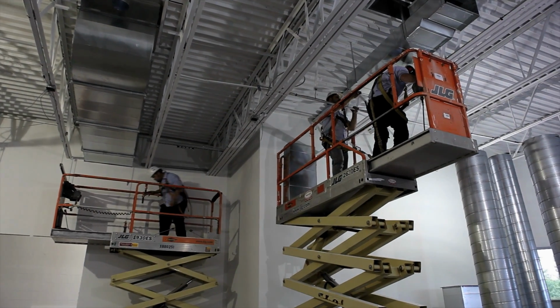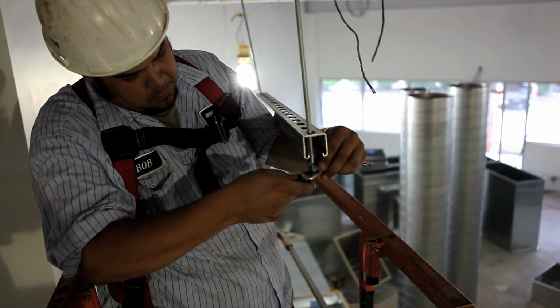If you look to my right, you'll see gridwork up top. Inside that gridwork will be class 1000. That gridwork holds a curtain that comes down, creating positive air pressure in there, which is what allows us to get class 1000 with separate filtration. Any space that isn't within a grid space will be class 10,000 in here.